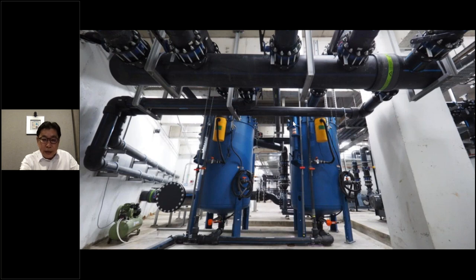So when you're stepping on the media, you're stepping onto the laterals as well, and also the mushroom laterals. So there are chances to break those laterals. Then without knowing, without properly checking, you put in your media, run the system, and the media goes back to the pool. Then you dig out everything and start all over again. These are frequent problems. I think a lot of us have encountered this issue.